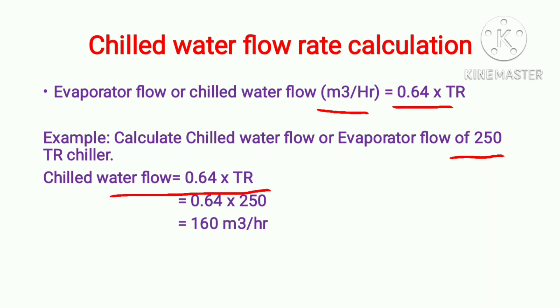We put the values: 0.64 into 250 TR — this is the capacity of our chiller. After calculation we are getting 160 meter cube per hour. This is the chilled water flow rate for that chiller.